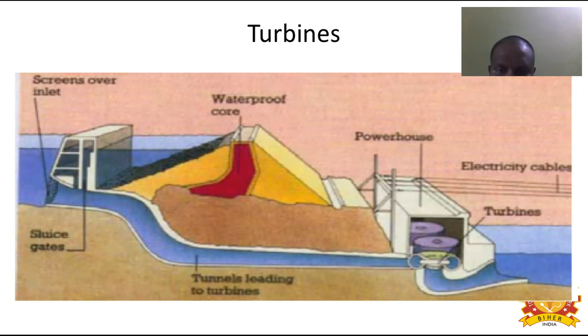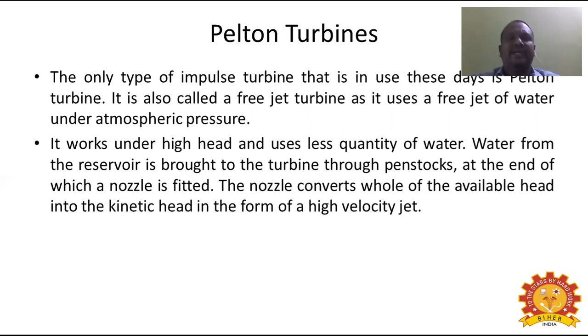The Pelton wheel is the only type of impulse turbine, as opposed to reaction turbines, and is also called a free jet turbine. The turbine uses a free jet of water at atmospheric pressure. It works under high head. The water from the reservoir is brought to the turbine through a penstock, at the end of which a nozzle is fitted. The nozzle converts the whole of the available head into kinetic head, forming a high velocity jet. This is the Pelton wheel diagram.